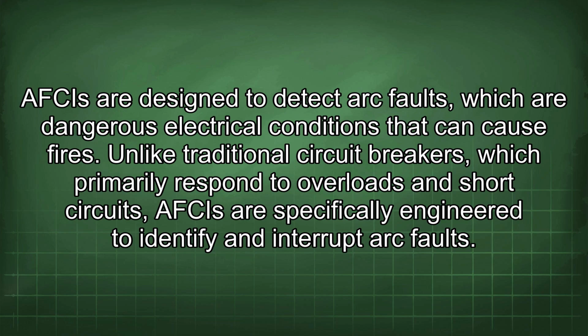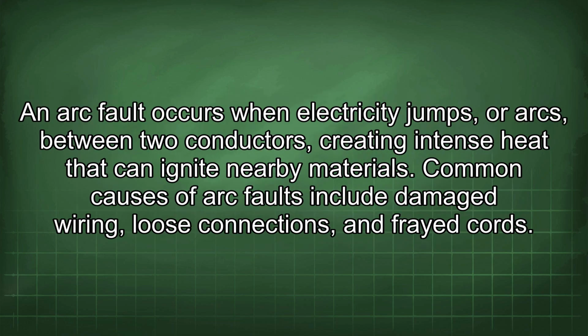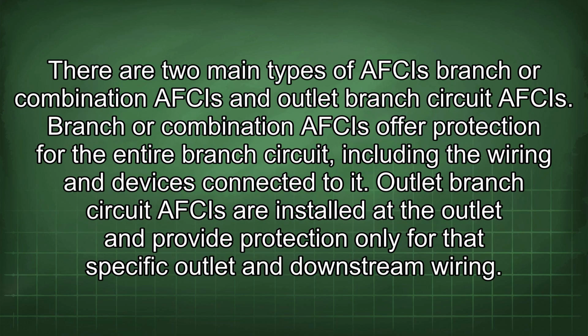Unlike traditional circuit breakers, which primarily respond to overloads and short circuits, AFCIs are specifically engineered to identify and interrupt arc faults. An arc fault occurs when electricity jumps, or arcs, between two conductors, creating intense heat that can ignite nearby materials. Common causes of arc faults include damaged wiring, loose connections, and frayed cords. There are two main types of AFCIs: branch or combination AFCIs and outlet branch circuit AFCIs.